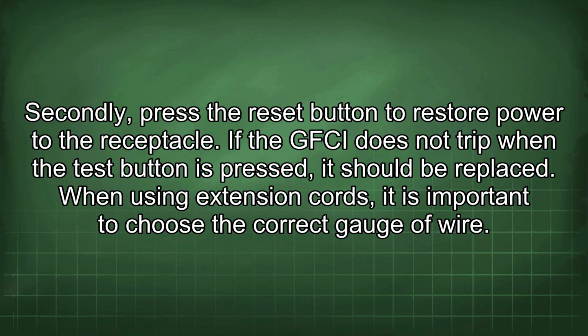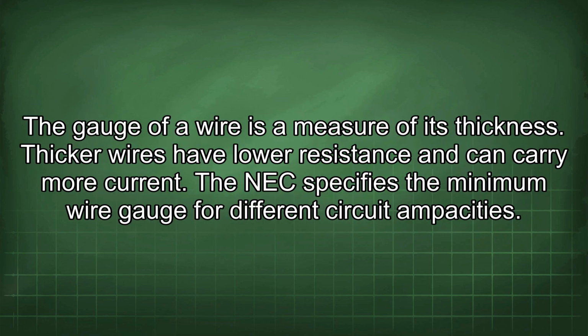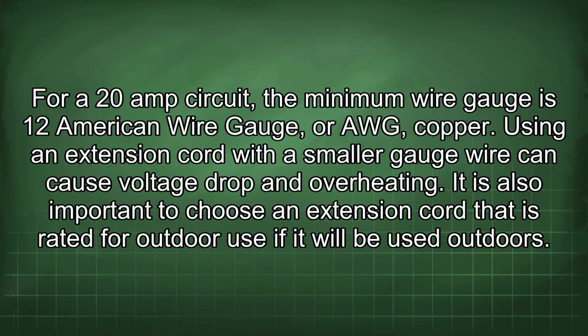When using extension cords, it is important to choose the correct gauge of wire. The gauge of a wire is a measure of its thickness. Thicker wires have lower resistance and can carry more current. The NEC specifies the minimum wire gauge for different circuit ampacities. For a 20 amp circuit, the minimum wire gauge is 12 American wire gauge, or AWG, copper.